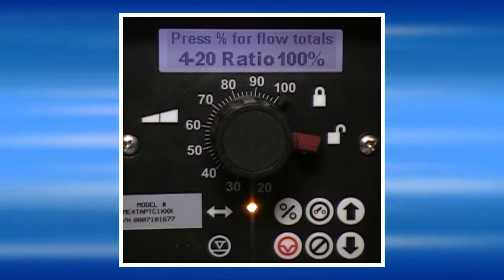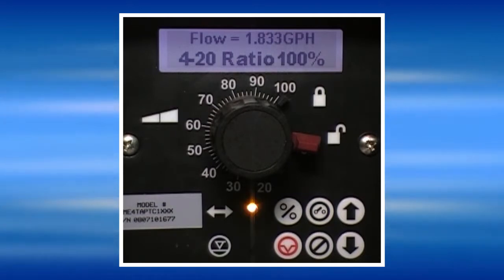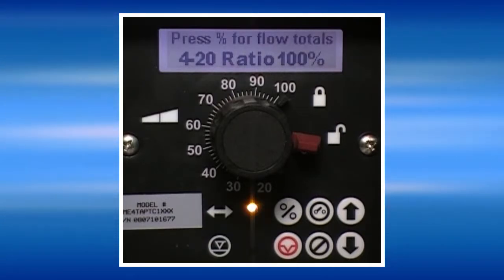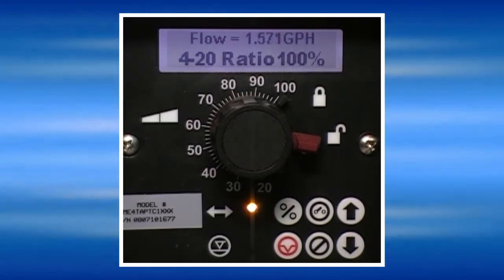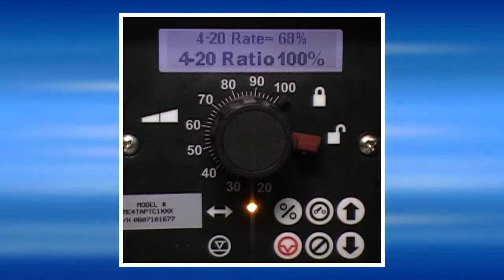When the pump receives 20mA, it runs at 100% speed. It displays its flow in gallons per hour, liters per hour, or gallons per day at the top of the screen. It will also display its current stroke frequency percentage. As the signal is gradually decreased from 20mA closer to 4, the pump's speed changes proportionally to the input.